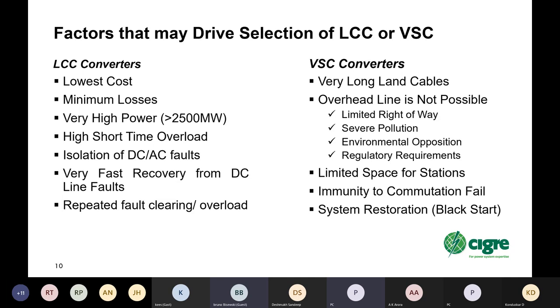LCC is also very good at isolating AC and DC faults because the fault clearing on the DC side is very, very fast. And also LCC gives very fast recovery from DC line faults, as well as the ability to provide repeated fault clearing followed by overloading to bring the system stability back in control. So those are the reasons that you might consider LCC converters.